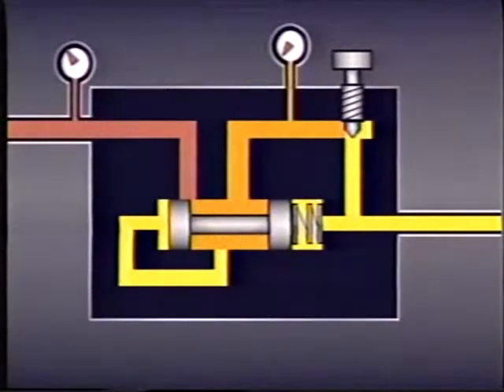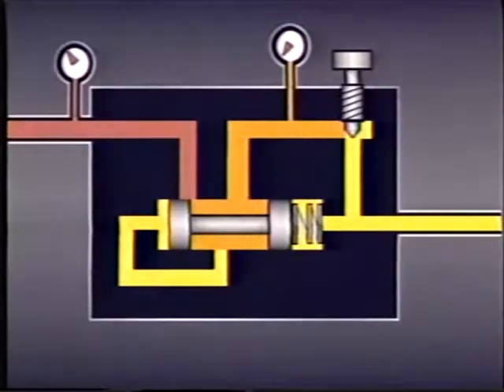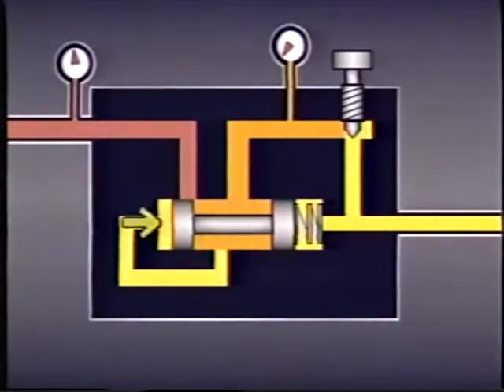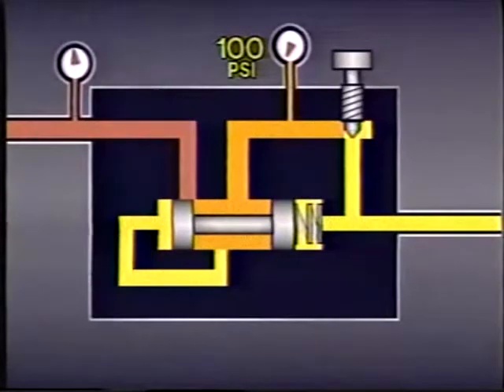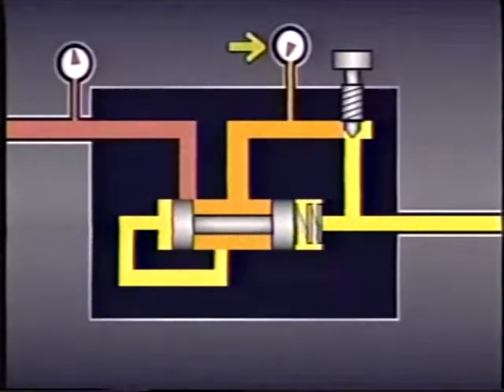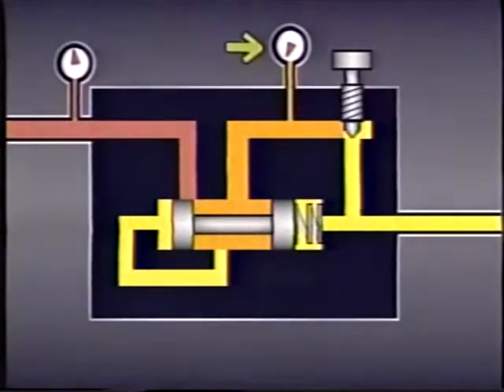The remaining 400 PSI is converted into heat and carried away by the fluid. If upstream pressure rises, the spool continues to shift. For example, if inlet pressure rises to 600 PSI, the spool will shift a little more. The smaller restriction will lower pressure downstream of the restriction to 100 PSI, and the remaining 500 PSI will be carried away as heat. As long as there is no load, the pressure just downstream of the restriction will equal the pressure of the spring. The difference between this pressure and the inlet pressure is always converted into heat.